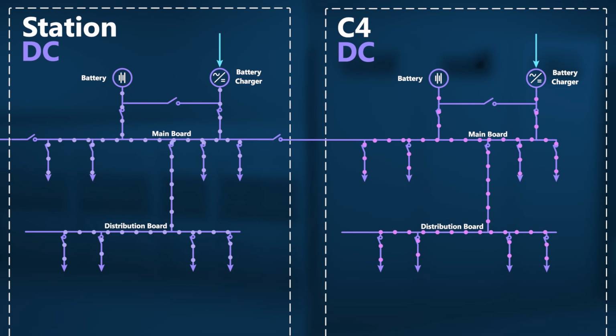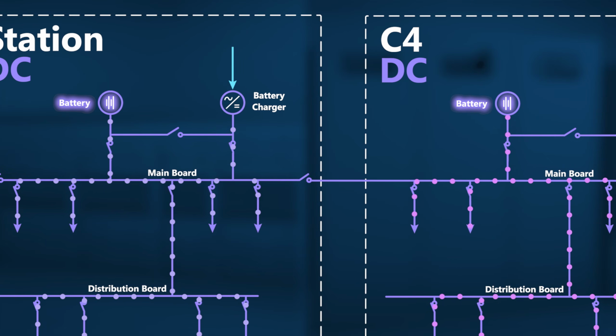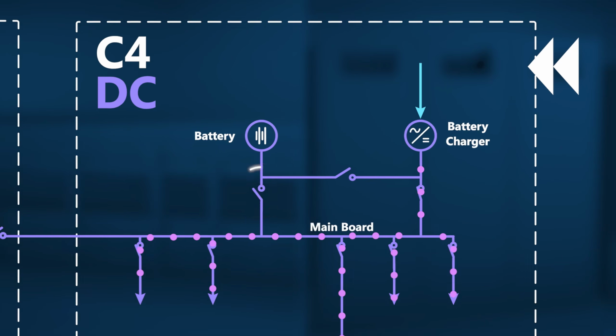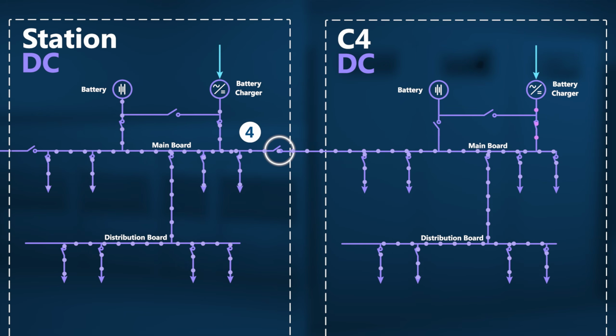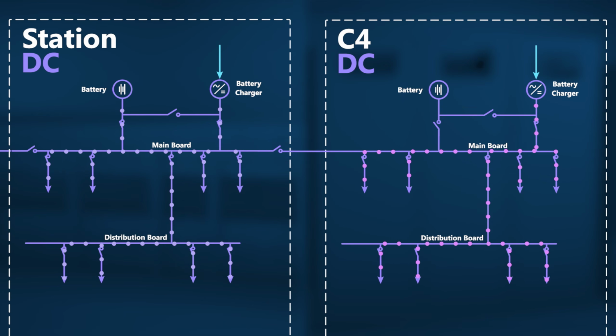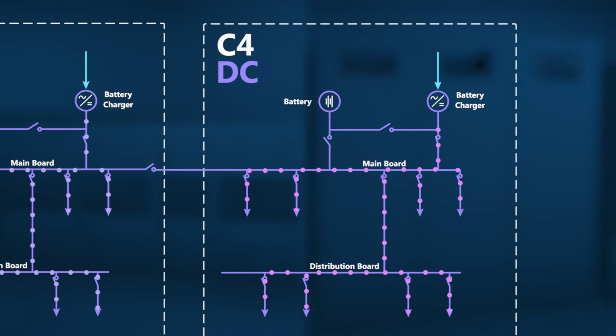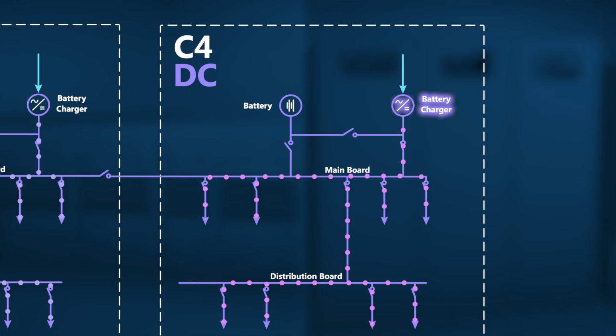The plant has physical safety measures specifically designed to prevent 2 batteries from being connected to the same system. This means station must be decoupled from C4 before the battery is reconnected. But this sequence does require that the C4 battery charger be the sole source of supply in between these 2 steps.